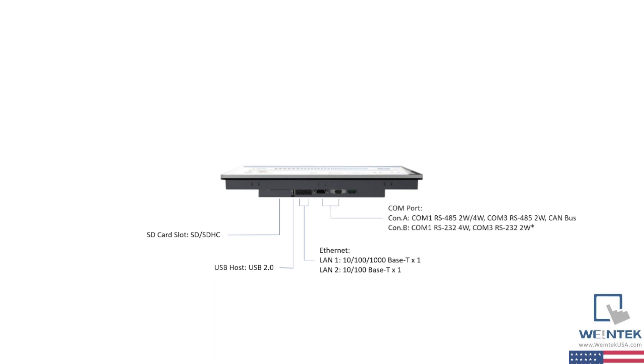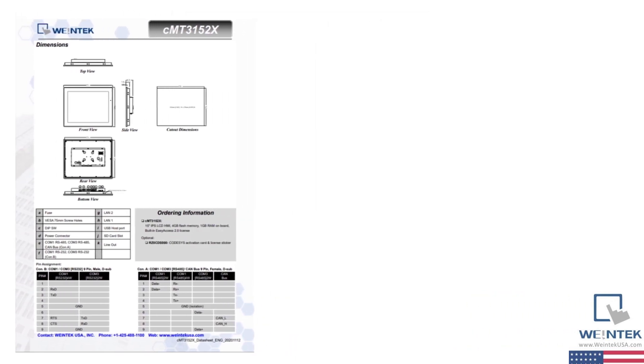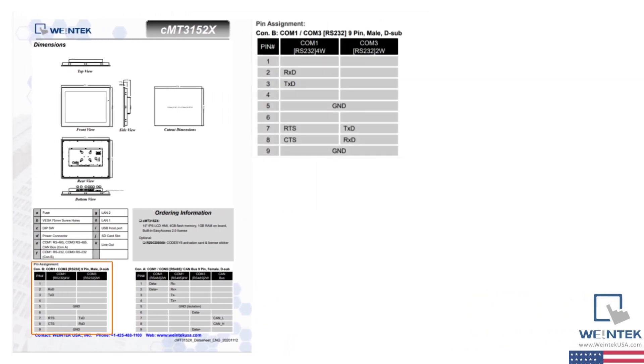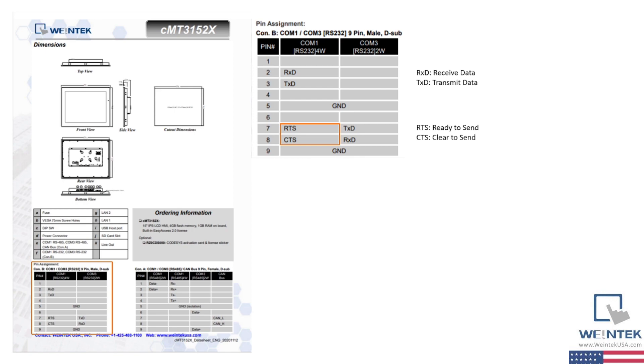The 3152X supports serial communication via an RS-232 and RS-485 interface, RS standing for recommended standard. Both RS-232 and RS-485 have 9 pins, some of which correspond to a method of communication. Within the RS-232 pin assignment, you will see RXD, TXD, RTS, CTS, and GND. RXD and TXD receive data and transmit data respectively, while RTS and CTS stand for ready to send and clear to send, while GND stands for the ground wire.